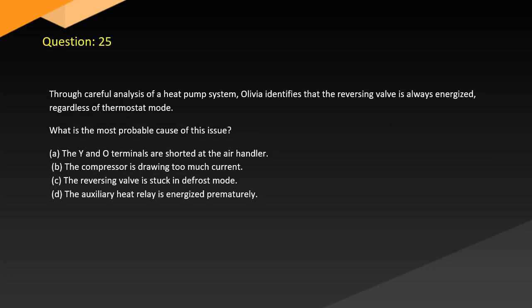Question 25. Through careful analysis of a heat pump system, Olivia identifies that the reversing valve is always energized regardless of thermostat mode. What is the most probable cause of this issue? A. The Y and O terminals are shorted at the air handler. B. The compressor is drawing too much current. C. The reversing valve is stuck in defrost mode. D. The auxiliary heat relay is energized prematurely.